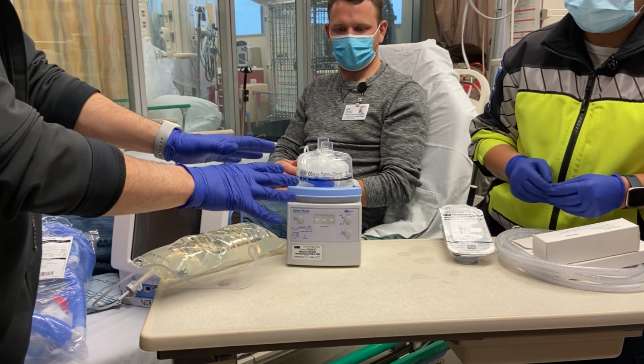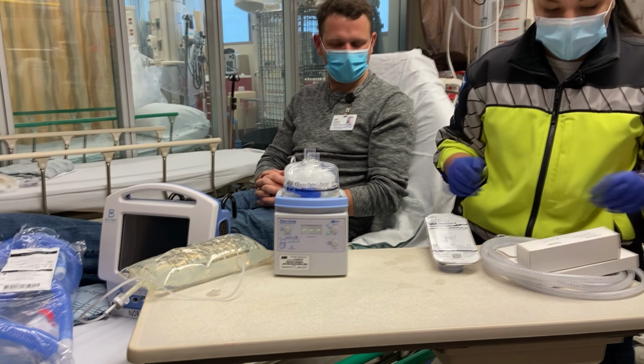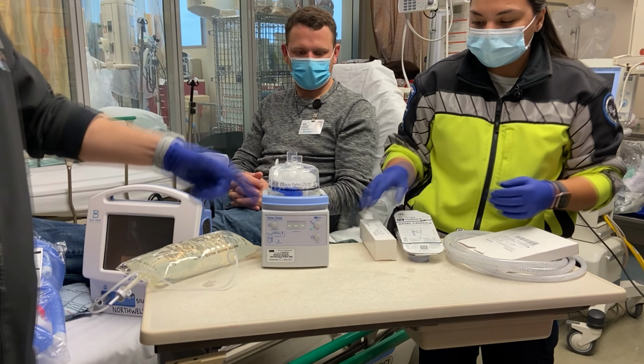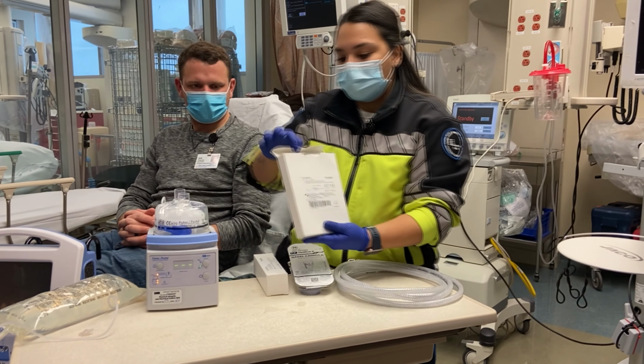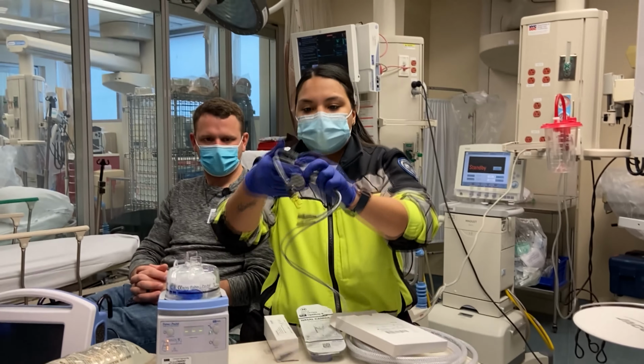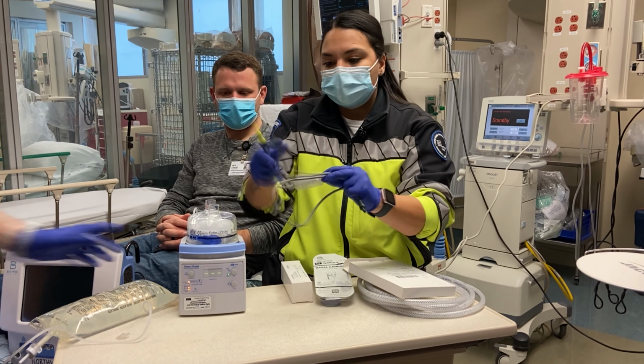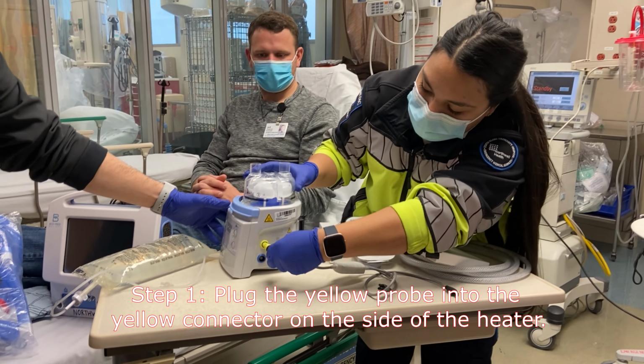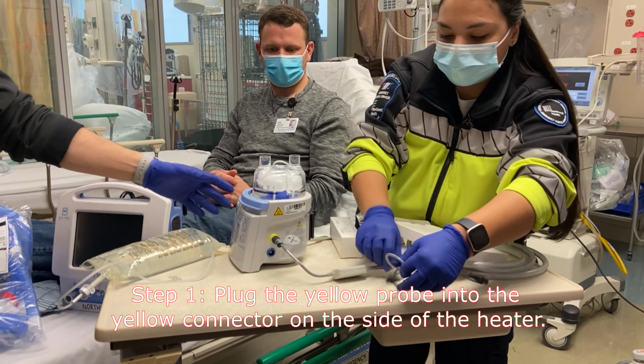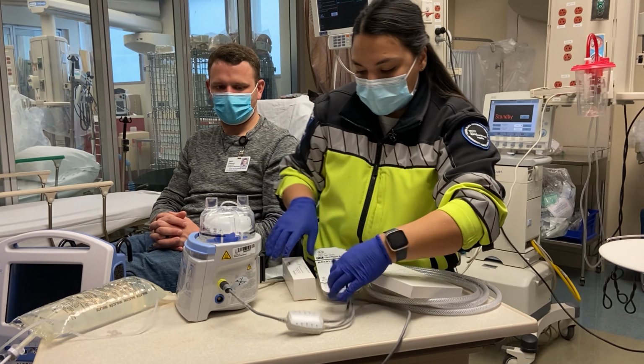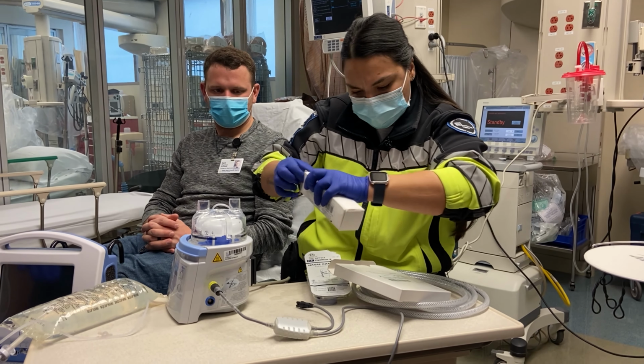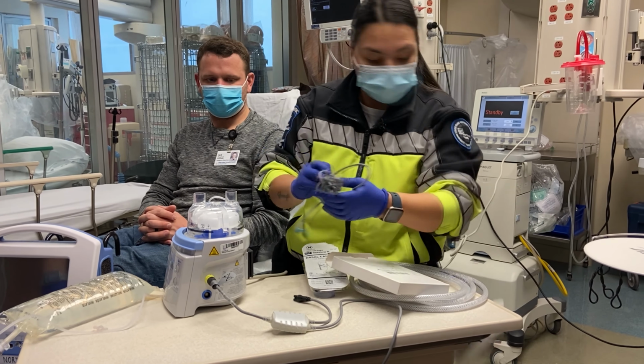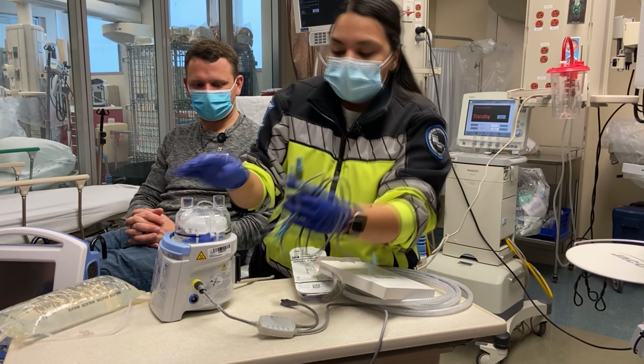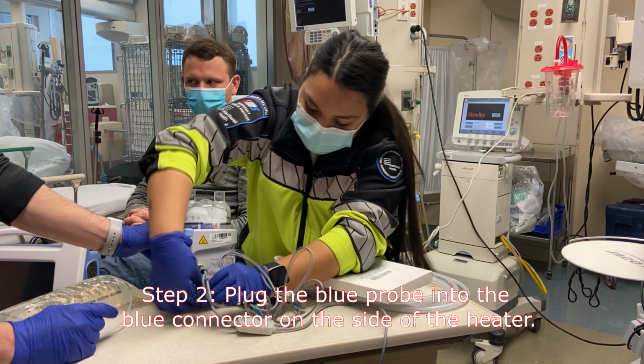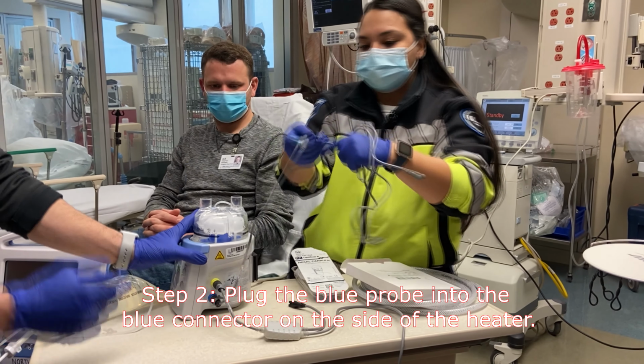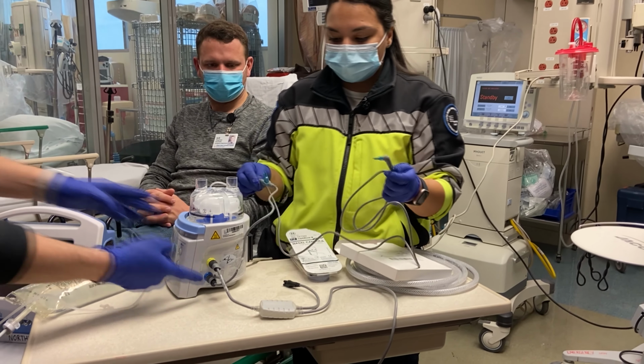The rest of this requires additional work to set up the heater, which we're going to demonstrate now. So the humidification point is done at this point. The heater has two items. So here, we have this set up here, your yellow prong, which will go on the side here. This is the device that provides heat to the circuit. And then you have this, the temperature sensor from the circuit to help the machine identify what temperature to reach. So this is essentially the thermostat in your house, whereas the yellow plug is the furnace in your house. Provides heat, senses heat.